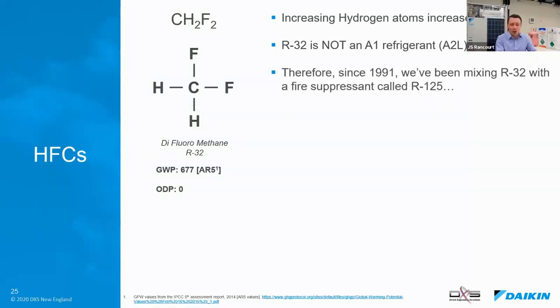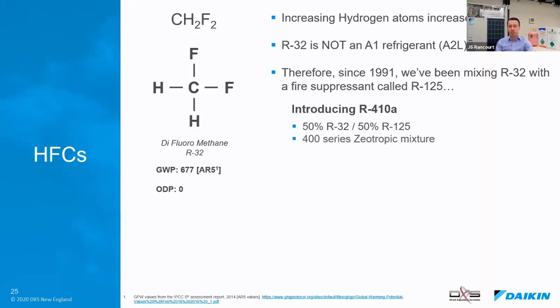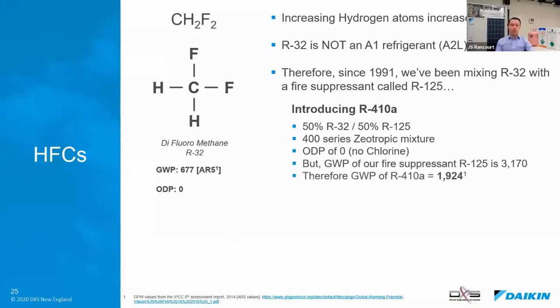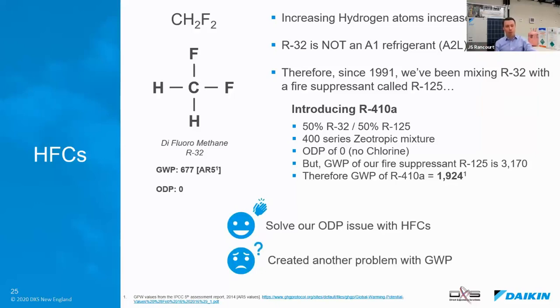So what that means is that since the early 90s, we've been taking this beloved high-efficiency R32 and mixing it with a fire suppressant, specifically R125, and that's how we made R410A. So R410A, this tank right here, has 50% R32 and 50% R125. It's a 400 series zeotropic mixture. It has no chlorine, so that's great. But that fire suppressant has a very high global warming potential, over 3,000. You mix those two together, the GWP of R410A is almost 2,000. So what happened is, we solved our ozone problems with HFCs like R410A, but we created another problem with the global warming potential due to the fire suppressants we have to keep adding to R32.